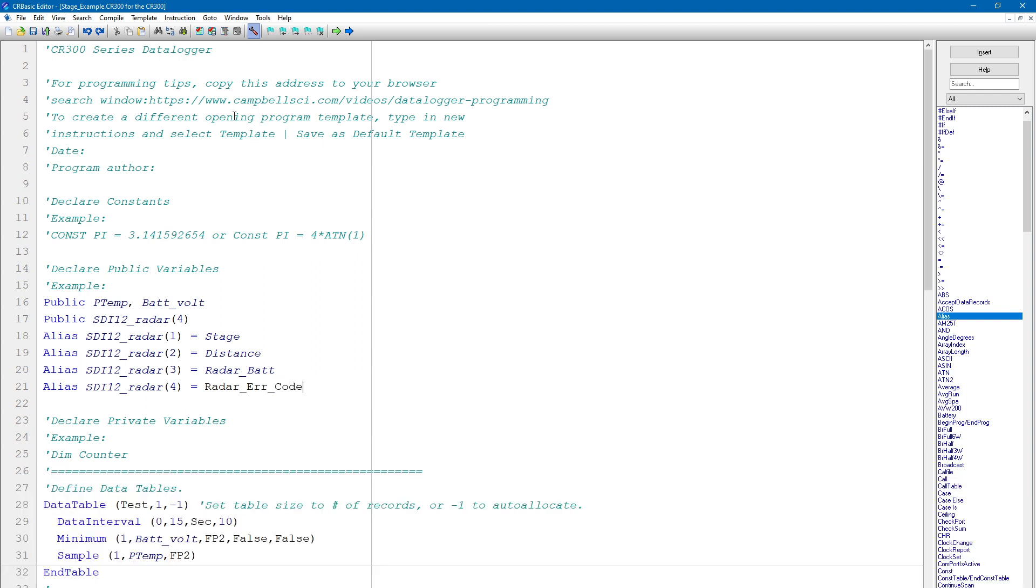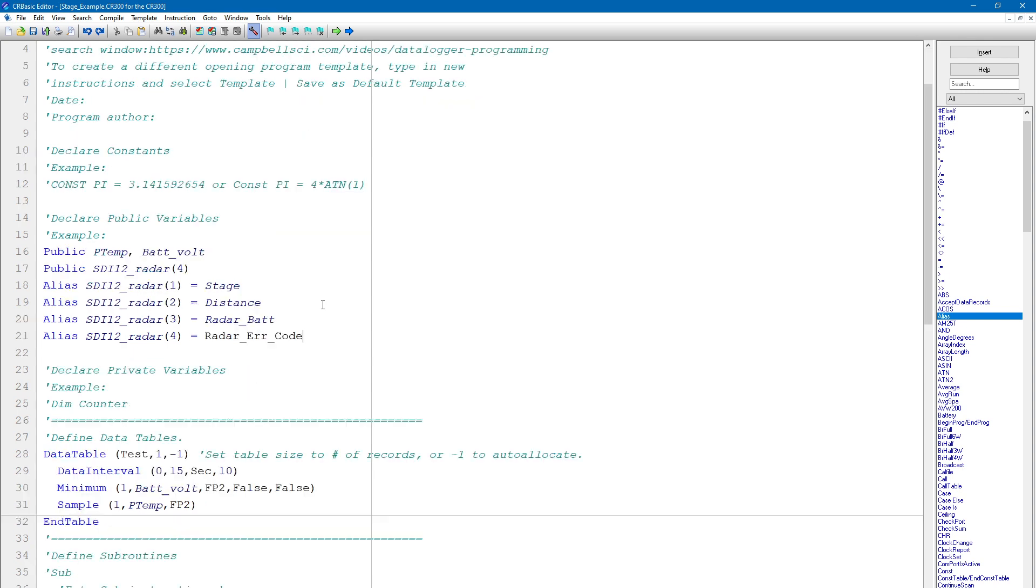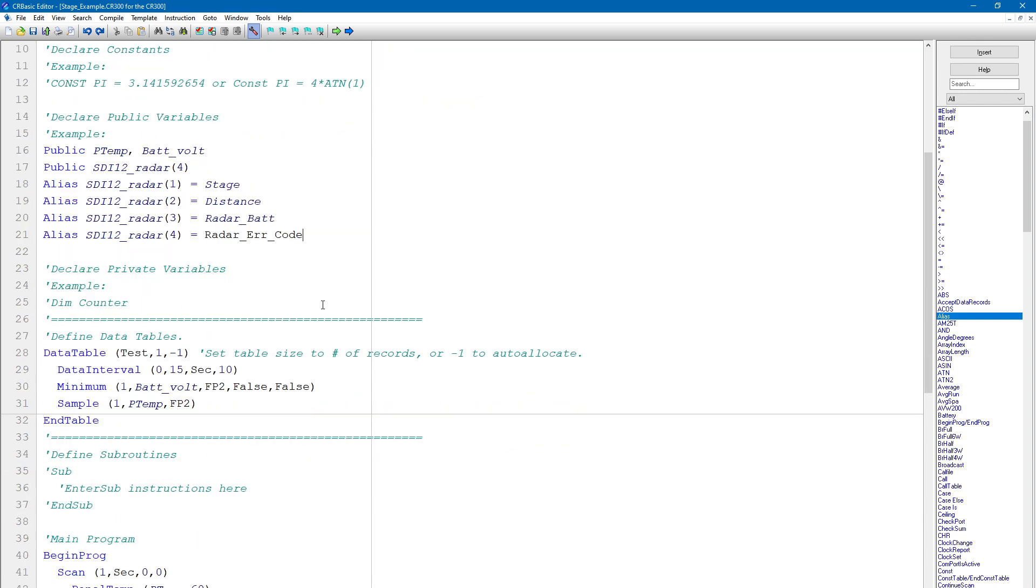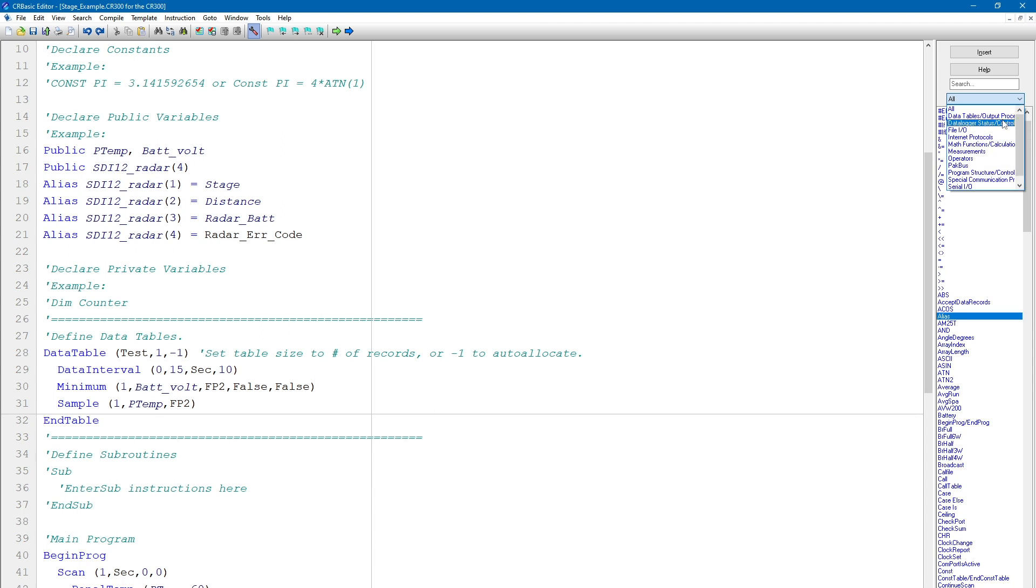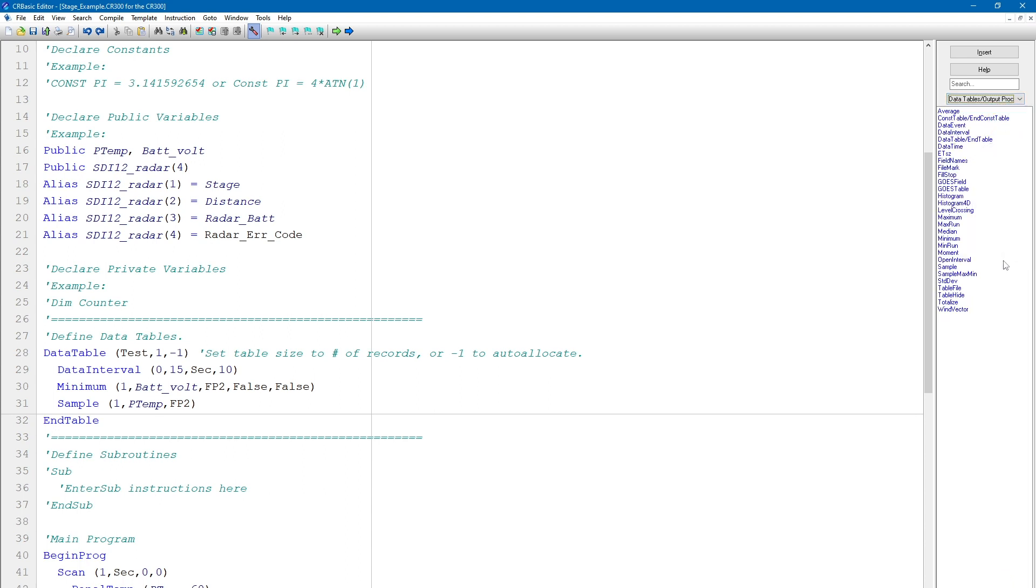Now I can refer to these variables by either their original name or their alias throughout the program. I am also able to view the aliases in the public table. Now that I have variables defined to store the sensor outputs, I need to configure a data table to store the outputs to final data storage. To see a list of CRBasic instructions that can be used for data table output and processing, select Data Tables Output Processing from the drop-down list at the top of the instruction window. When I set up a data table, I like to organize it so the primary data, or the data that I bought the data logger to measure, is at the top of the table.